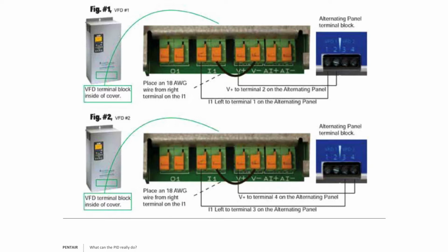So first of all, our alternator has its own power supply that powers the clock. So in this case here, the minute you plug it in, we start a 24-hour counter. And at the end of that 24 hours, it's going to make relays on the left lag and the relay on the right lead. 24 hours passes, and then 1 and 2 become lead, and 3 and 4, the connectors on the right, become lag. So if you're trying to shoot, for example, for a midnight change, you would have to plug the unit in at exactly midnight.